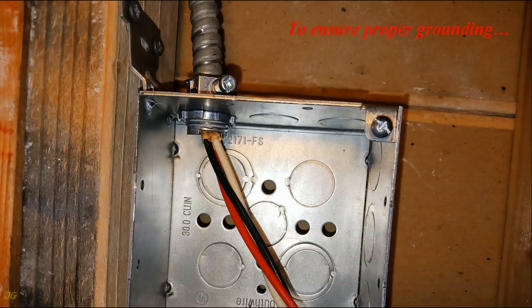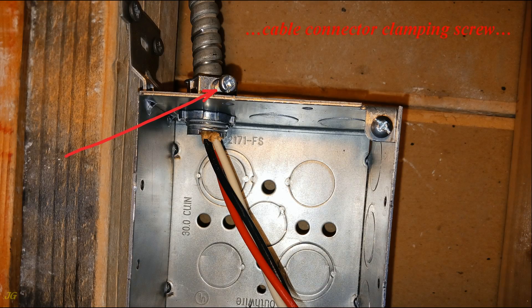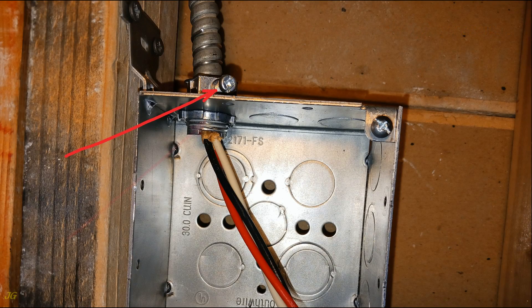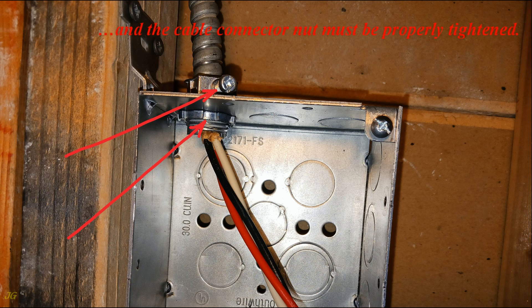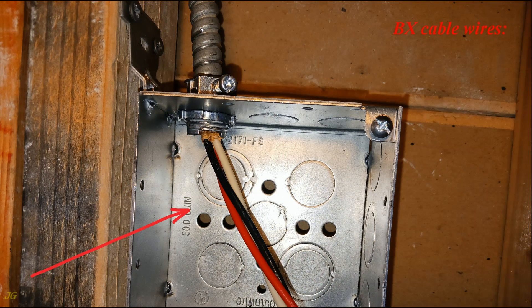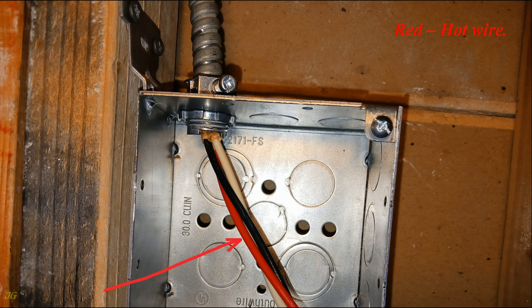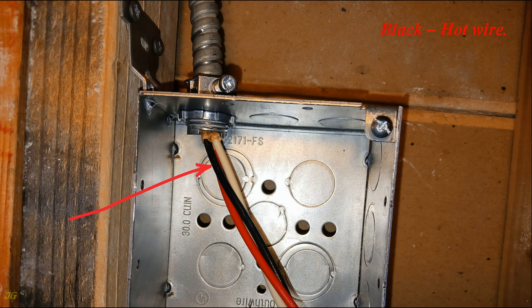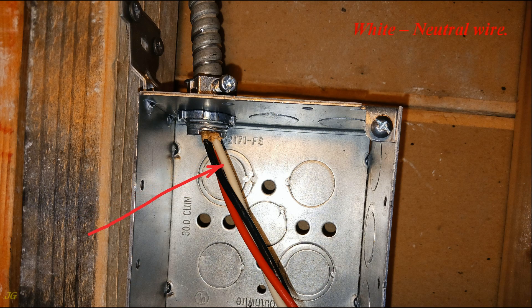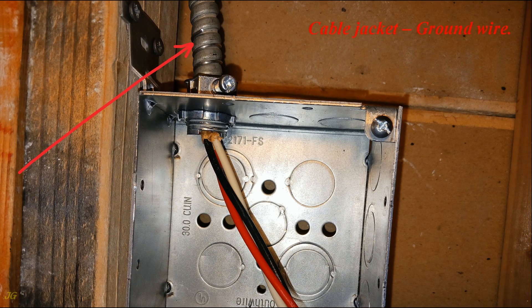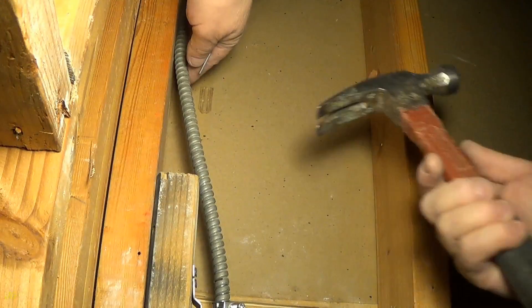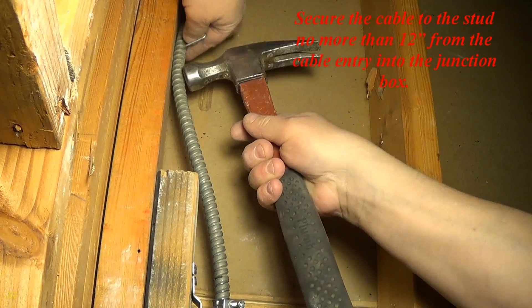To ensure proper grounding, cable connector clamping screw and the cable connector nut must be properly tightened. BX cable wires: red hot wire, black hot wire, white neutral wire, cable jacket ground wire. Secure the cable to the stud no more than 12 inches from the cable entry into the junction box.